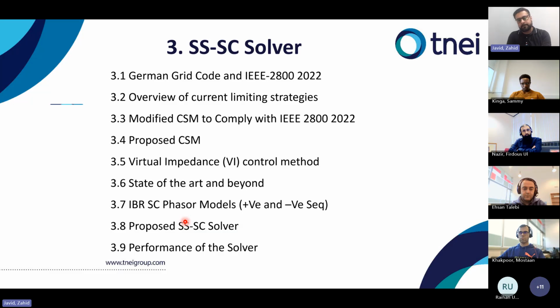Now, once we have developed that solver, we utilize it to develop the steady state short circuit solver for the IBRs. And how can we develop a current limiting strategy that can comply with the IEEE 2800? I will explain this standard later on, and also the German grid code. There was one publication that modified the current saturation method to comply with the IEEE 2800, but there were some limitations of that strategy, and we enhanced that strategy to strictly comply with this standard. And we also developed the virtual impedance control for the GFM to comply with this standard. And I will discuss what we did to go beyond the state of the art, and how we develop the IBR model in the phasor domain, in the sequence domain. And then I will show the proposed methodology of the solver, and I will show some results as well.